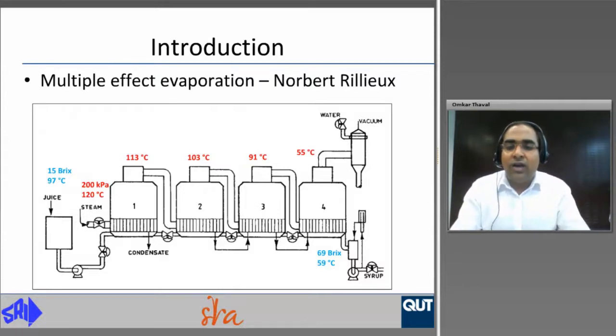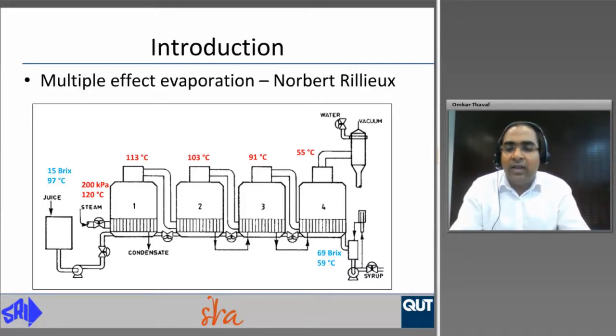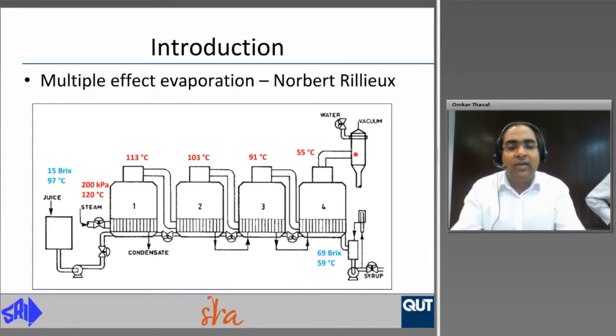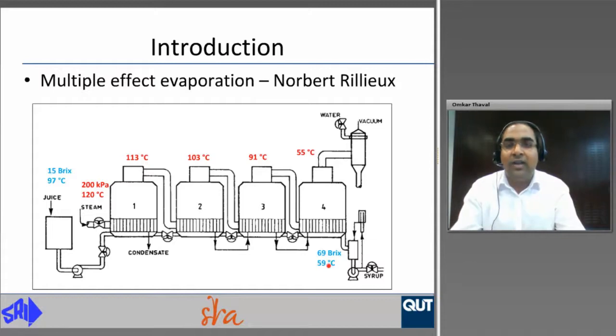Multiple effect evaporation was developed by Norbert Rillieux in the Louisiana sugar industry to achieve efficient usage of steam. The figure shows a quadruple effect where juice at 15 brix and 97 degrees Celsius is brought into the first effect and heated with process steam at 120 degrees Celsius. Using the graduated pressure difference between the process steam and vacuum in the final effect, vapour in the first effect heats the juice in the second effect and so on, until the final effect where vapours are condensed in the barometric condenser. The syrup leaving the final effect is at 69 brix and 59 degrees Celsius.